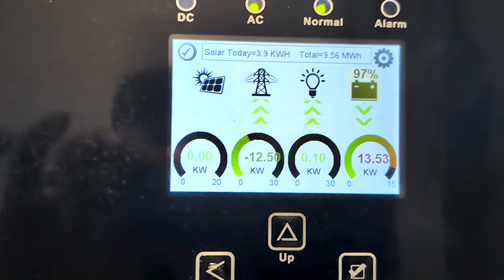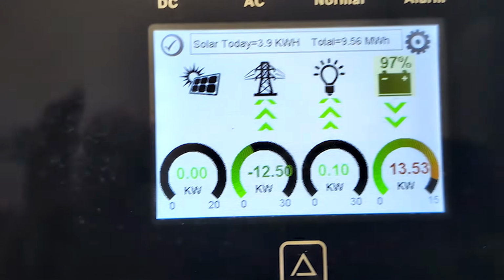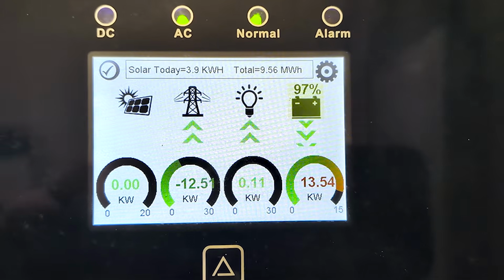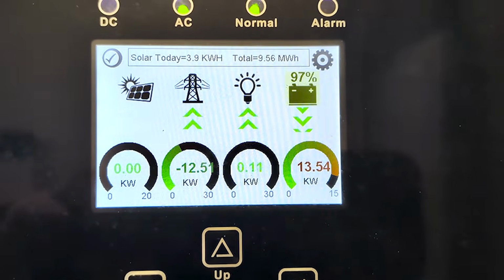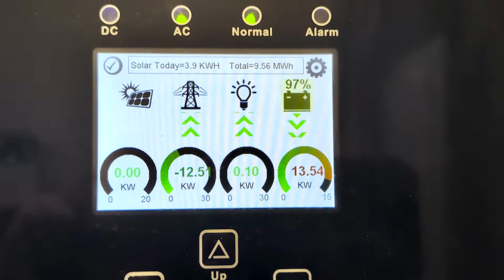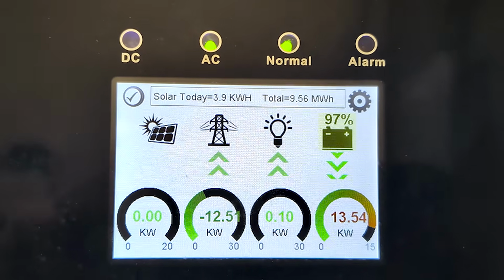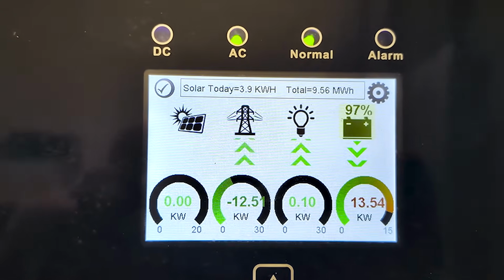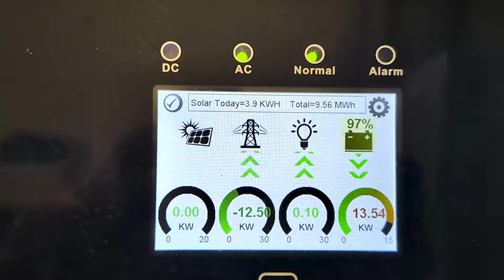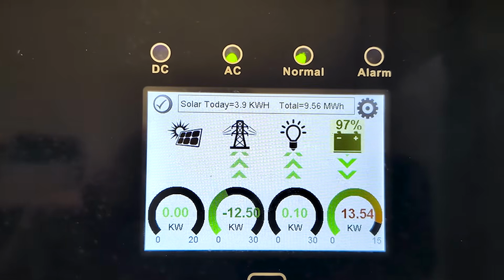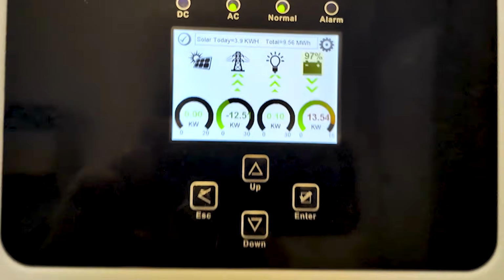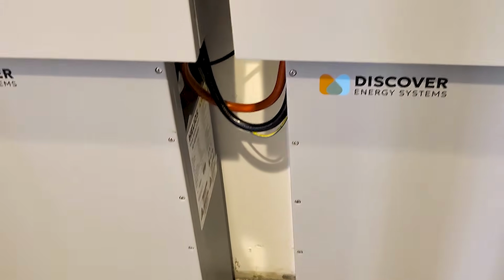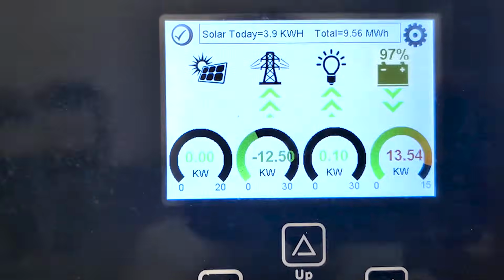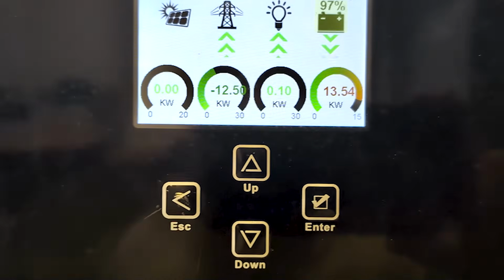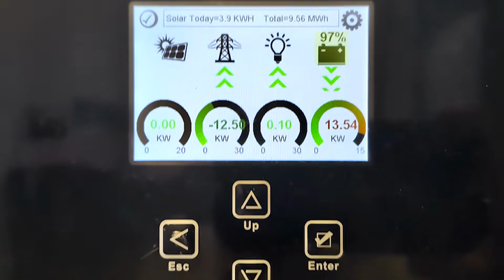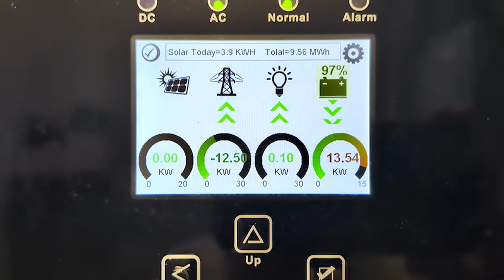So doing a continuous battery dump, battery only, running 12.5 kilowatts. I'm dumping back on the grid, selling battery. I turned all the loads off except for the inverter itself, which runs about 100 watts. So I'm dumping 12.5 back on the grid, pulling 13.5 out of the batteries. Again, it's only 2 Helios, so I can't do that all day, but just to show you - started at 9 o'clock, and we'll see how far it runs. That's what I'm running on 12.5.